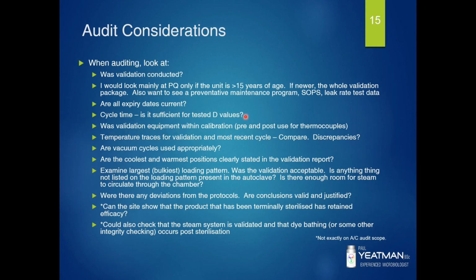So here, there's no point doing a validation on the autoclave if your thermocouples haven't been calibrated or your biological indicators expired, say, 3 months ago. You could do counts on your indicators, which would extend the validation period, but that would depend on whether or not that was allowed by your internal procedures. Some sites allow it, some don't. But you would need to document it and show that your expired strips or solution haven't expired. Are vacuum cycles used appropriately?